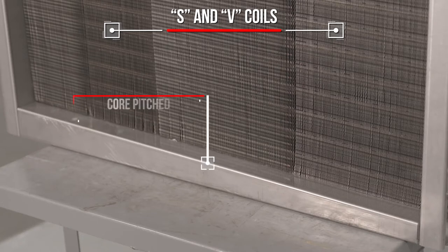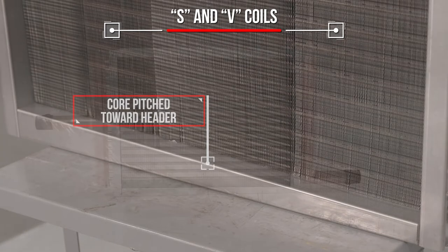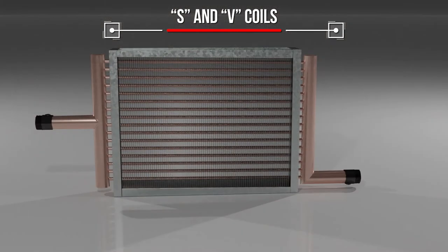S and V cores are pitched within the casing toward the condensate header to ensure reliable liquid removal, even when the coil is placed out of level.